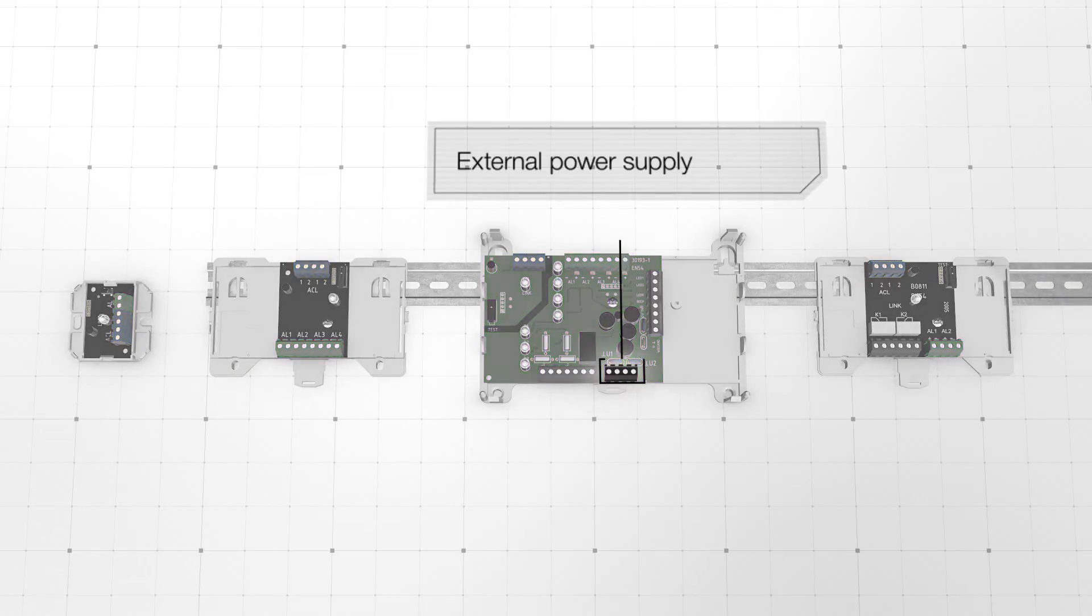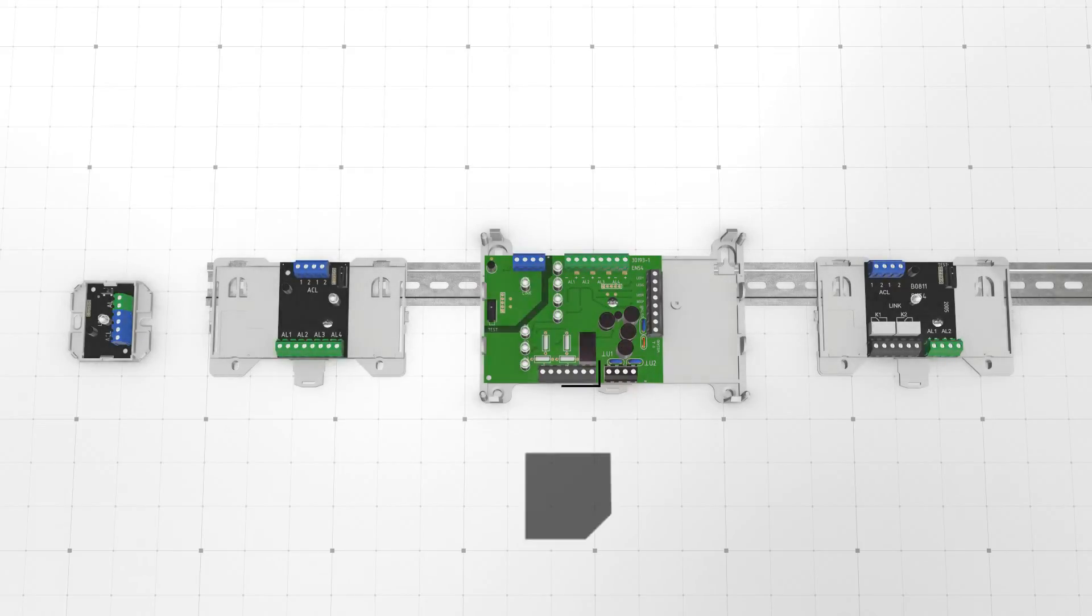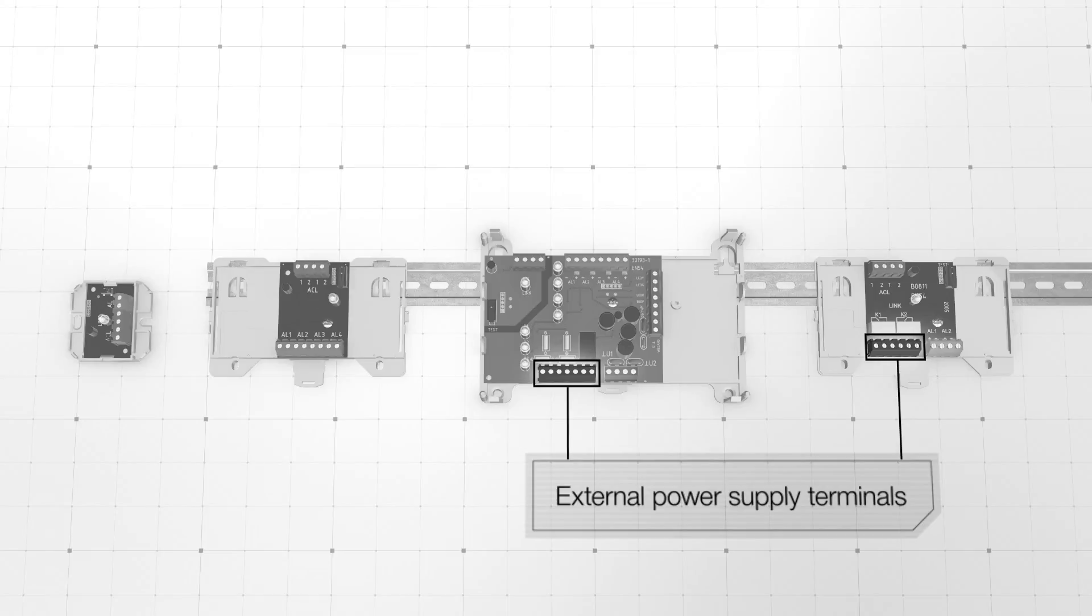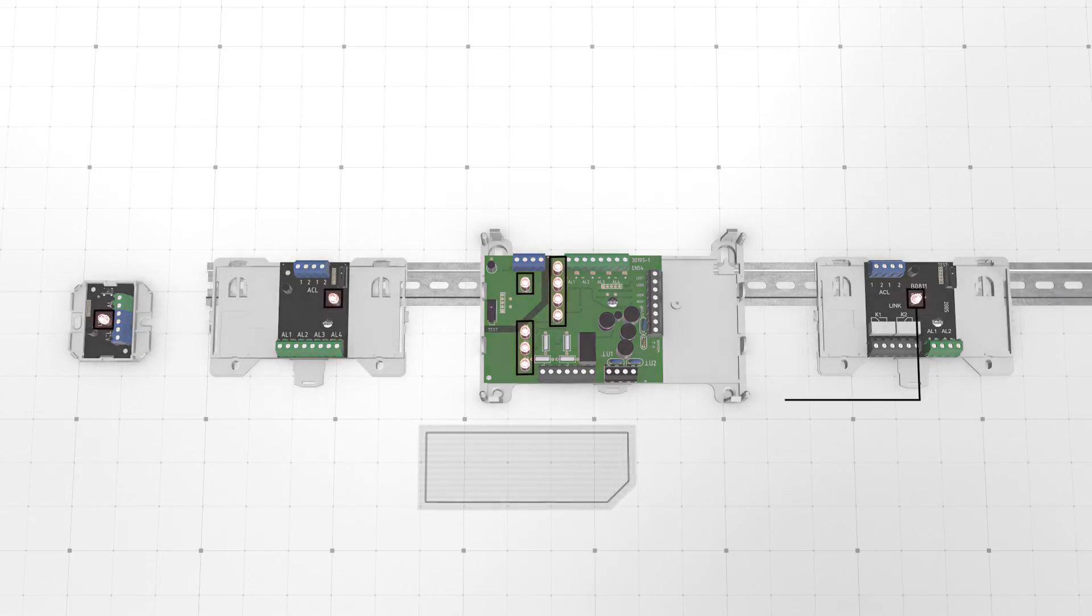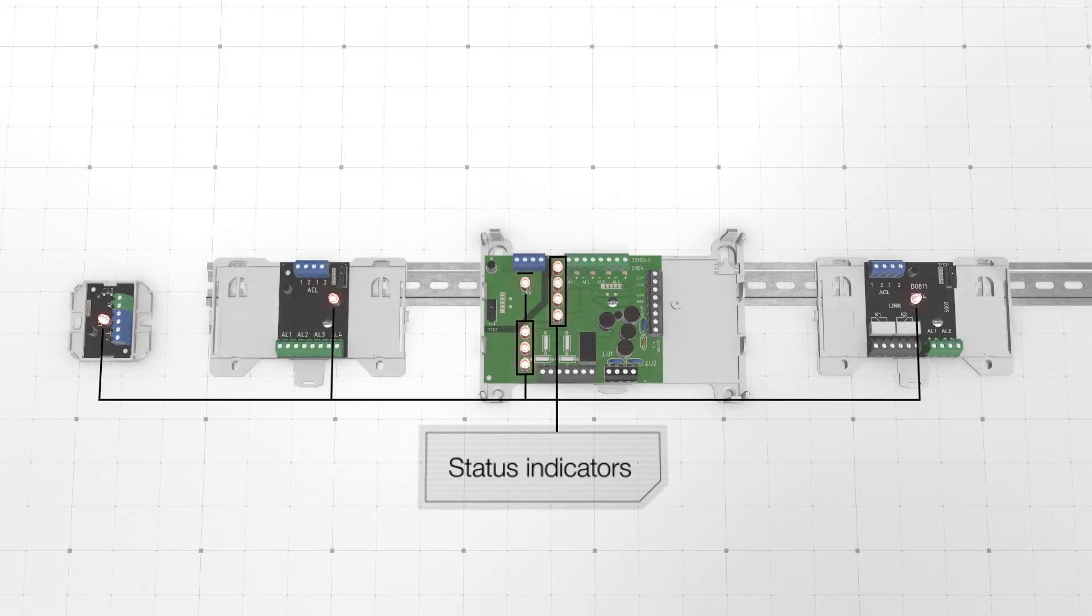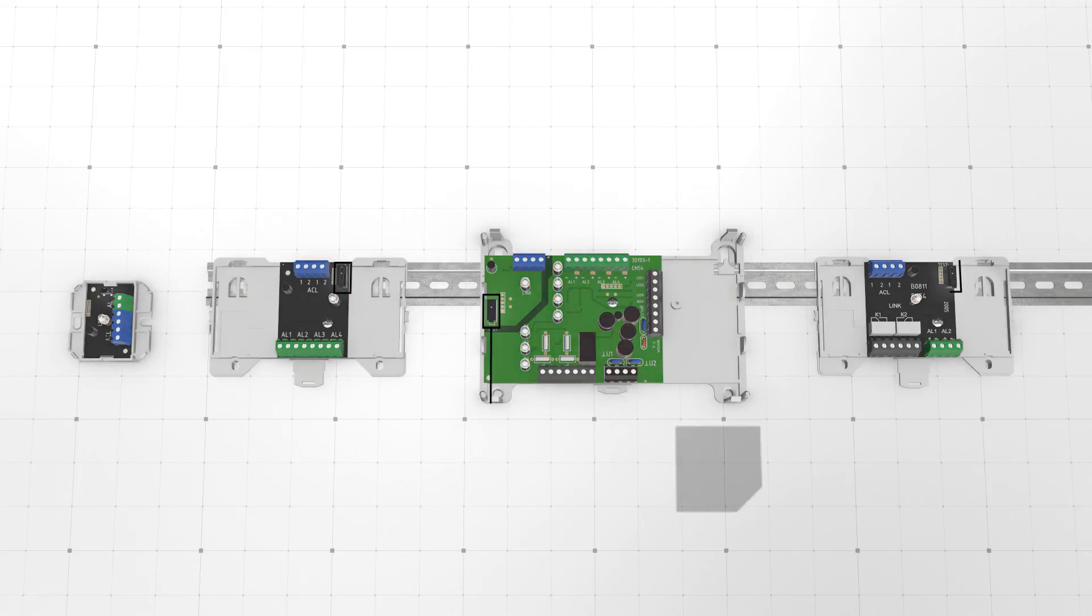The black-colored external power supply terminals, available only on IOCM43, are used to connect 12 or 24 VDC external power supply. The gray-colored relay and output terminals with circuit integrity control, available only for IOCM43 and IOM22, are used to connect external controlled devices. Each module's PCB also has indicators displaying the status of outputs and of connection with control panel.